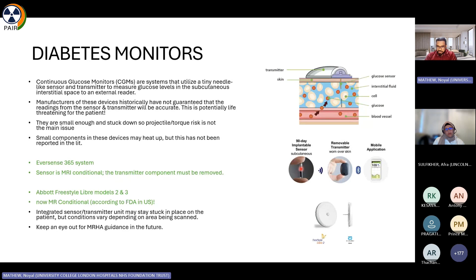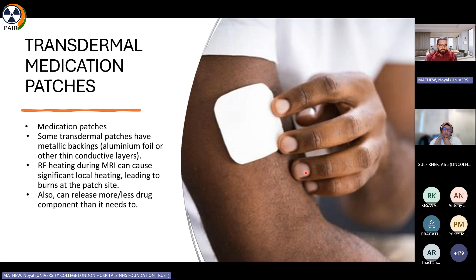Transdermal medication patches. One reason why we don't want these patches is that they have a metallic coating within them, so that they can be antimicrobial, or so that they can stick to the patient's body better and so on. So we don't want that aluminum or silver layer to heat up the patient. The second reason is that the RF from the MRI can lead to it inadvertently releasing more drug than it needs to, or less drug than it needs to. So if a patient had a fentanyl patch, it could lead to over-release, or a menopausal lady with a hormonal patch could have more hormones being given depending on their body heat increase, thereby causing sensitive body parts like sensitive nipples and so on. So that's the reason why we ask them to remove this.